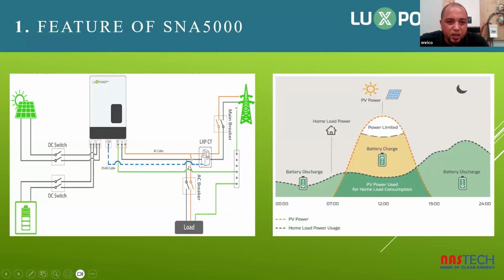Now with the LXP CT clamp, you measure the direction of the grid flow to the inverter. So this LXP CT clamp is used in the exporting to grid. The SNA also has the exporting to grid feature. To enable the exporting to grid feature, you need the LXP CT clamp.